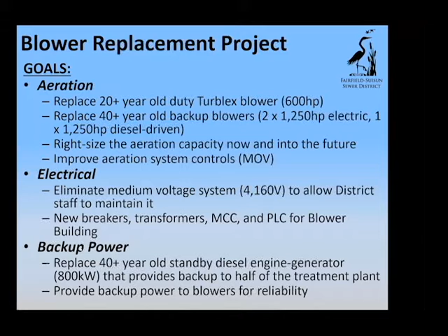The electrical equipment in general was just as old as the rest of the system, so we replaced much of that. In terms of backup power, the blower building also housed a large 800 kilowatt diesel generator that provided backup power to about half of our plant. That was also original to the plant, and we needed to replace it for reliability purposes. We also increased the size so it could now provide electrical backup power to our new blower system.